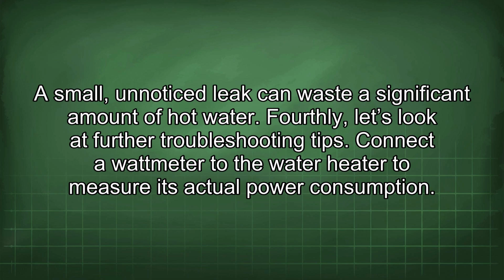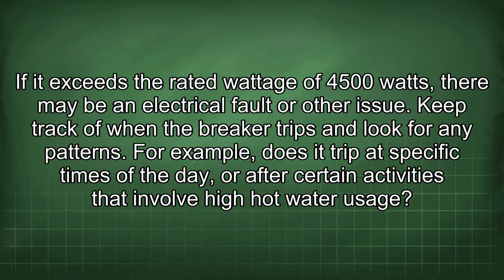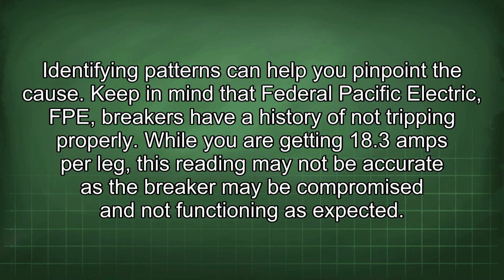Fourthly, let's look at further troubleshooting tips. Connect a wattmeter to the water heater to measure its actual power consumption. If it exceeds the rated wattage of 4,500 watts, there may be an electrical fault or other issue. Keep track of when the breaker trips and look for any patterns. For example, does it trip at specific times of the day or after certain activities that involve high hot water usage? Identifying patterns can help you pinpoint the cause.